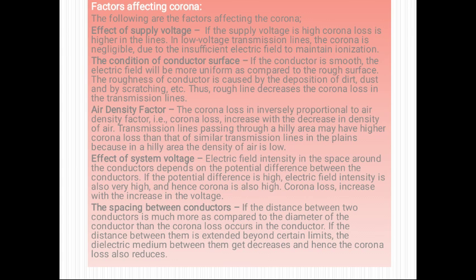Next is air density factor. The corona loss is inversely proportional to the air density factor. That is, corona loss increases with the decrease in density of air. A transmission line passing through a hilly area may have higher corona loss than a similar transmission line in the plains because in hilly areas the density of air is low. We know that in hilly areas air density is low, pressure is also low. So corona loss becomes higher.